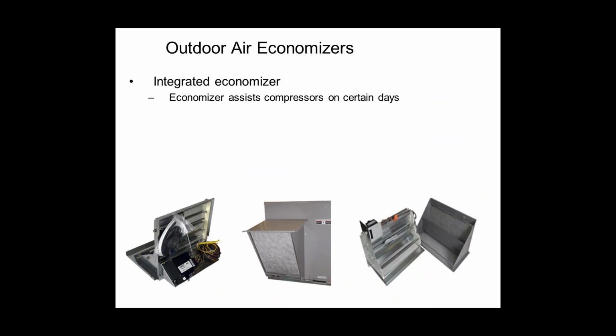A couple of things on economizers too. We have to do an integrated economizer. That's required by code. I'll show you the language requiring that here in a second. Integrated economizer means that you have to have the ability to run the compression in conjunction with the outside air for cooling. So it's kind of like first stage is use the outside air. If it's cool enough, use the outside air as your first stage of cooling.